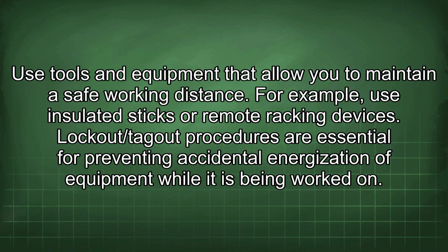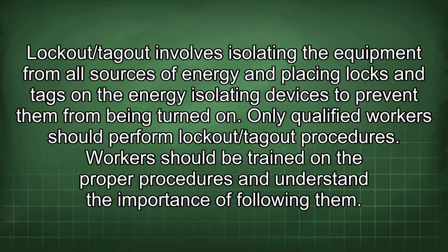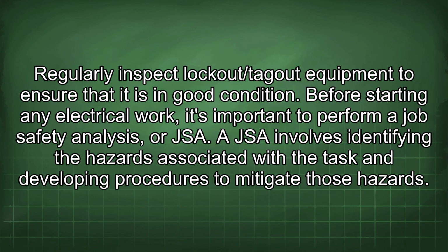Lockout/tagout procedures are essential for preventing accidental energization of equipment while it is being worked on. Lockout/tagout involves isolating the equipment from all sources of energy and placing locks and tags on the energy isolating devices to prevent them from being turned on. Only qualified workers should perform lockout/tagout procedures. Workers should be trained on the proper procedures and understand the importance of following them. Regularly inspect lockout/tagout equipment to ensure that it is in good condition.